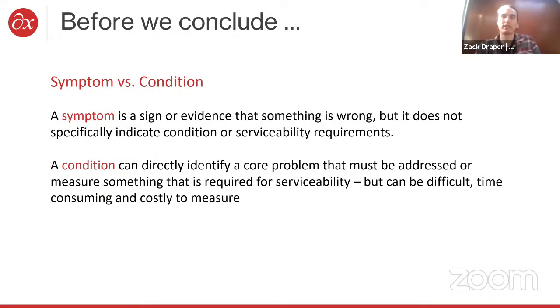A condition is something you can physically measure. For example, you can measure the power factor in a transformer, which tells you how well that transformer is insulating when it's under load. That's an actual condition measurement, something you can use to make rigid decisions on—it tells you whether a transformer is serviceable or not.